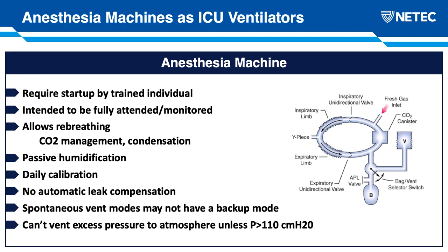And lastly, one of the big differences is that in the setting of an obstruction or a patient being desynchronous with the ventilator, the pressure often doesn't pop off until we see really high pressure, sometimes in excess of 110 centimeters of water. So ensuring that there's synchrony with the patient is very important when using at least some subset of our anesthesia machines.